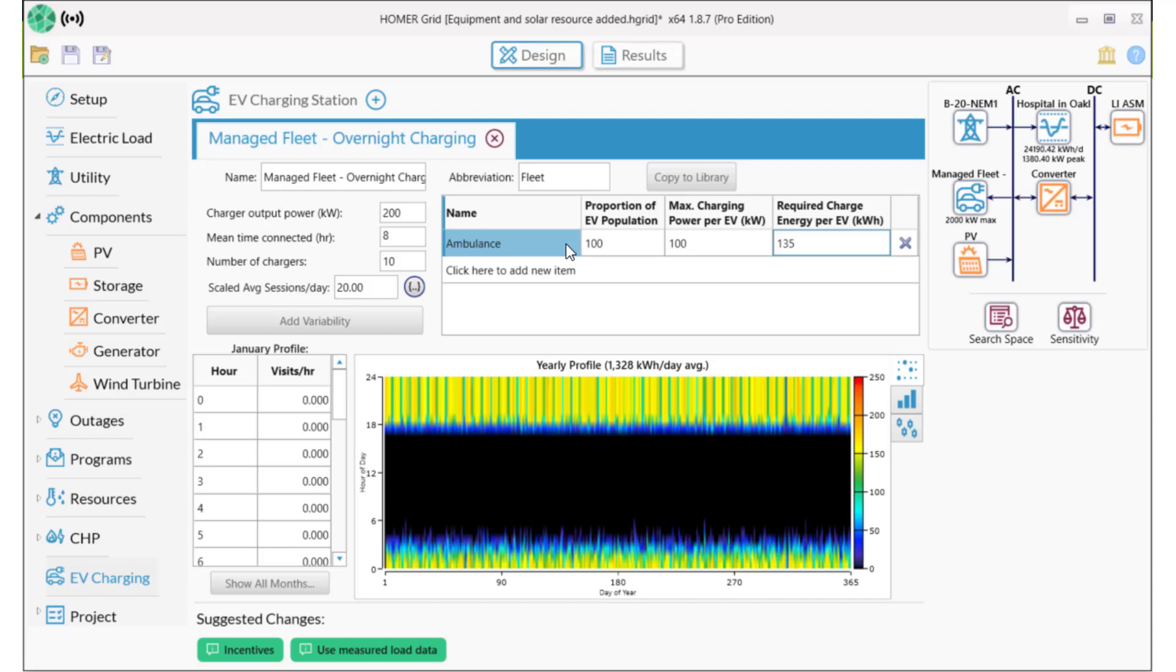So now we can see our charging load profile. It's adding 1,328 kWh per day on average to our load, up to a maximum of 2,000. So we've essentially doubled the peak load for this facility overall.